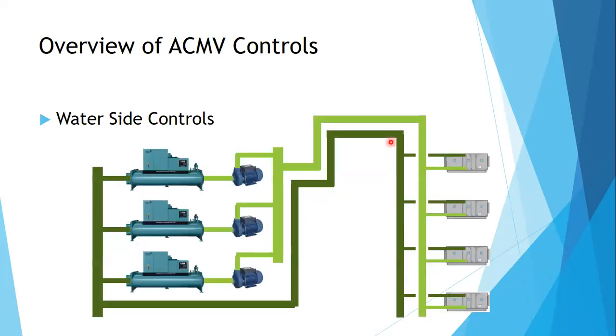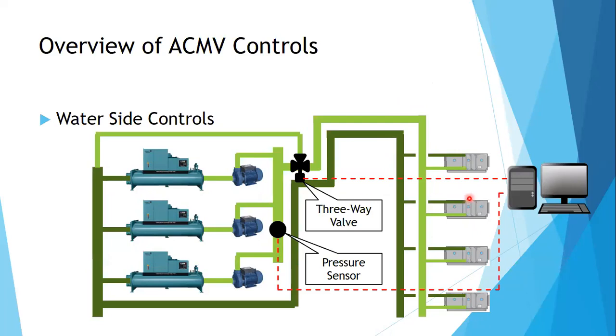Okay, next. Chilled water side. Assuming now that you have 4 air handling units, and you have 3 chillers. Why 3 chillers? Like our previous example, you have 2 duty, 1 standby. To ensure that the water is enough for all the air handling units, you also have a pressure sensor. Now, this pressure sensor ensures that these pumps are supplying enough water to all air handling units.